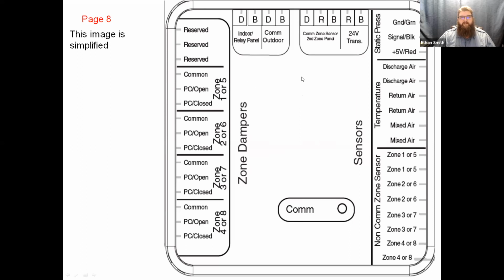So this is just a close-up of all of our wiring connections. So in here you see your data and your common from your indoor unit or your relay panel, whichever the case may be. We've got our data and common if we've got a communicating outdoor unit. This is where we're going to hook up all our communicating zone sensors if we have them. Now these terminals will usually only accommodate 2 pieces of 16 gauge wire or 18 gauge wire. So they give you these little guys. Let me flip my camera over here. Show you these clamps that they give you in the kit.